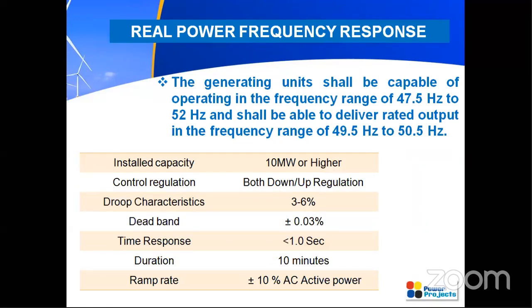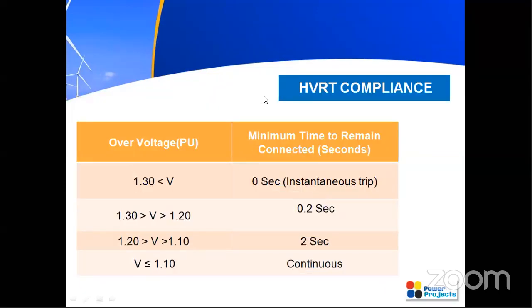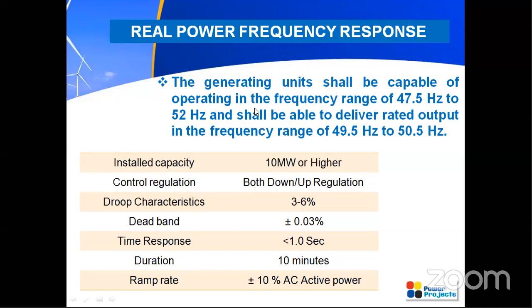And coming to the most important point, real power frequency response, I already stressed this point. The wind generating units shall be capable of operating in the frequency range of 47.5 hertz to 52 hertz, and they can deliver their output in the frequency range of 49.5 hertz to 50.5 hertz. This is a very important thing, but all these are subject to a condition. This is what the condition listed in the table is. I will explain this table in detail.